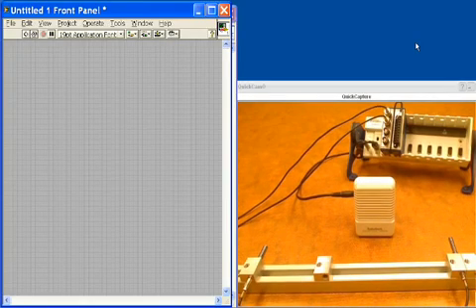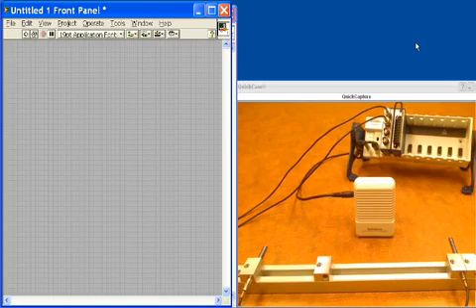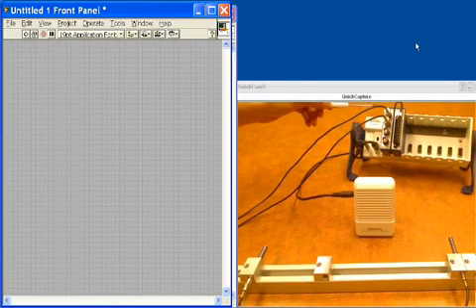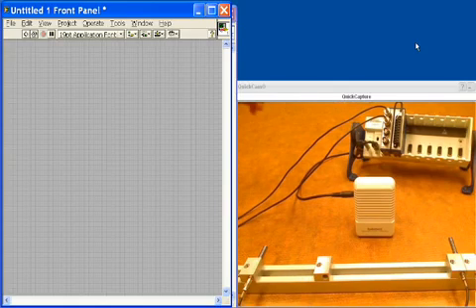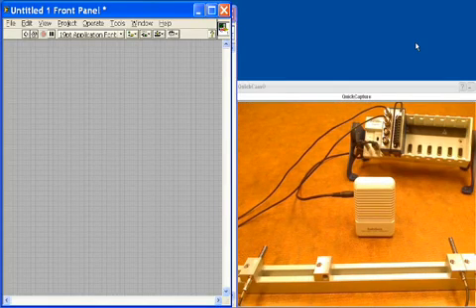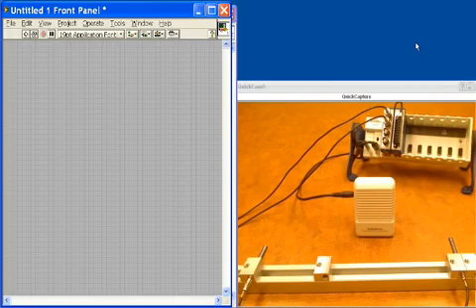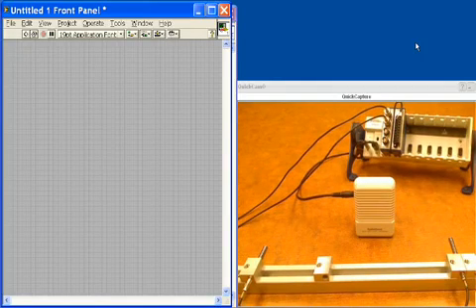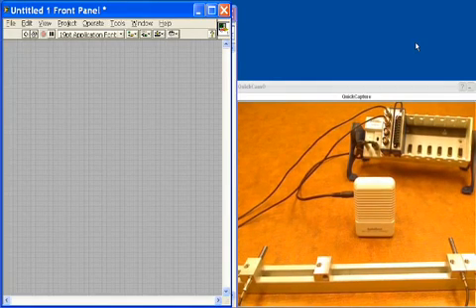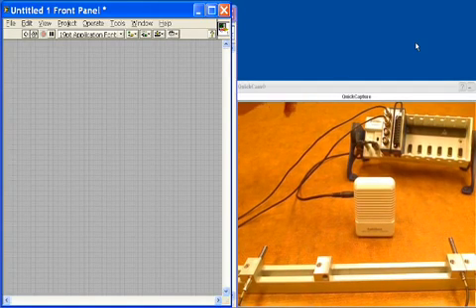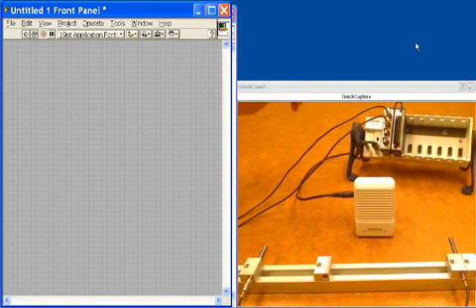What we have are two microphones, and these microphones are going to be acquired with the National Instruments C-Series 9233 data acquisition module. This is a 4-channel IEPE 24-bit module that can sample all 4 channels simultaneously at 50 ks per second per channel. The microphones are read into this module and we'll be acquiring them that way.